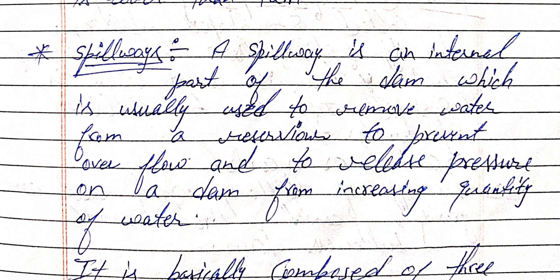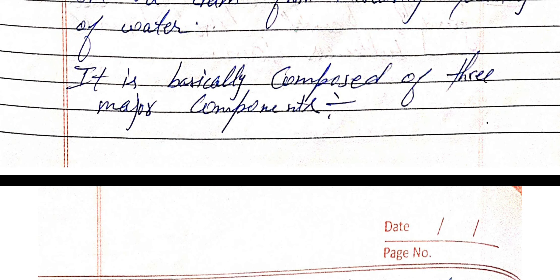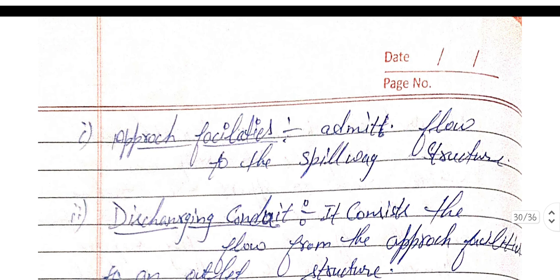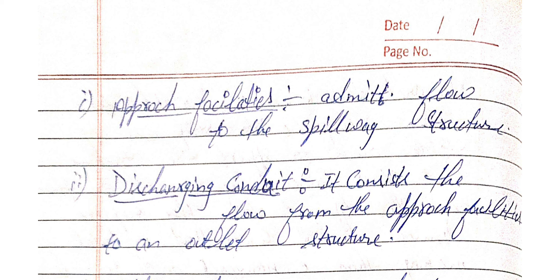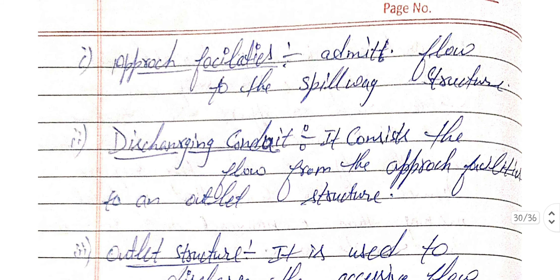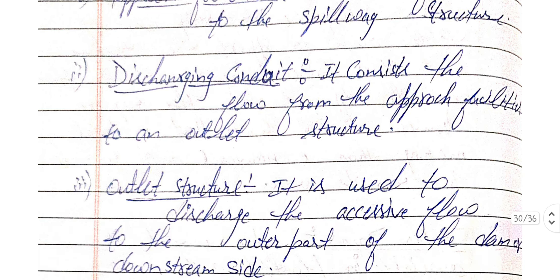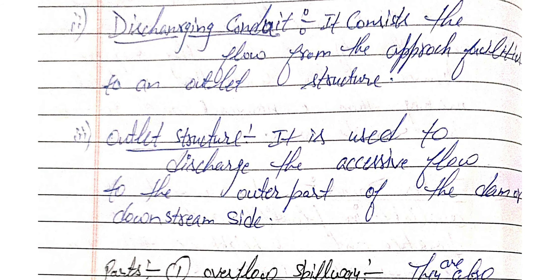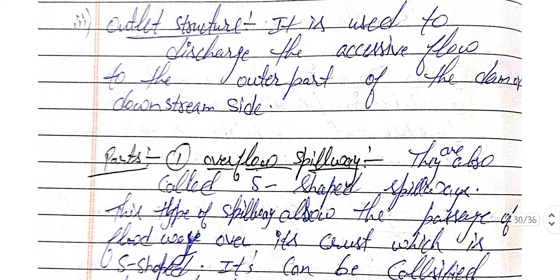The next topic is the spillway. A spillway is an integral part of the dam which is used to remove water from a reservoir to prevent overflow and to release pressure on a dam from an increasing quantity of water. It is composed of three major components: first, the approach facility, which admits flow to the spillway structure; second, the discharging conduit, which conveys flow from the approach facility to an outlet structure; and third, the outlet structure, which discharges excessive flow to the downstream side.